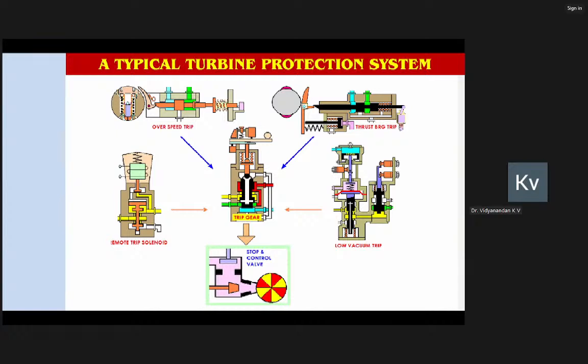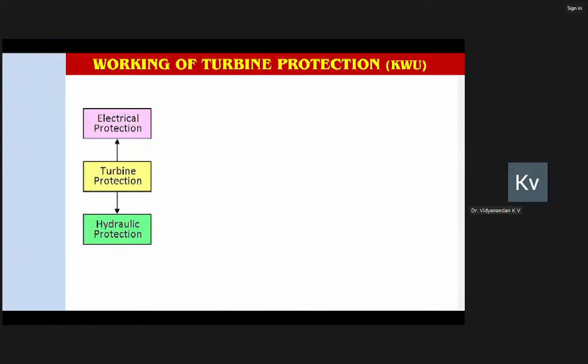Whenever any protection operates, like suppose the turbine lube oil pressure has collapsed, fire protection has operated, or axial shift exceeded, in that case the remote trip solenoid will operate. Normally, it will be in de-energized condition. At the time of tripping, it will energize and cut off the oil which is going to the trip gear. When the trip gear oil supply is cut off, it will cut off the trip oil, the red oil. And that trip oil is responsible for the stop and control valve and the NRV. So finally, operation of any protection, irrespective of the nature, mechanical, electrical, hydraulic, the trip gear will operate. Trip gear operation will drain the trip oil. Draining the trip oil will cut off the oil supply. So this is the way the turbine protection operates.